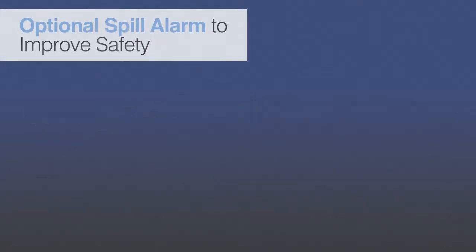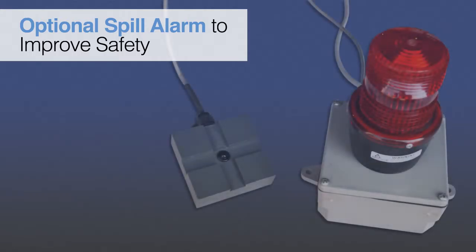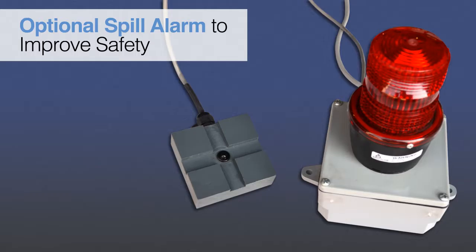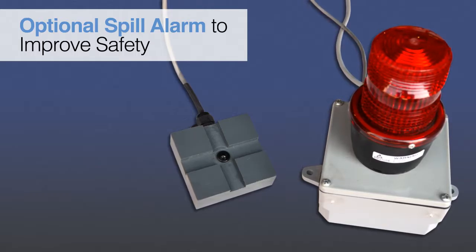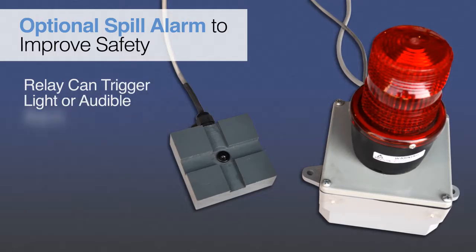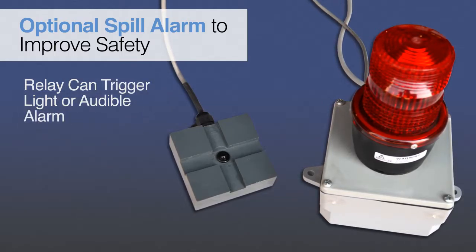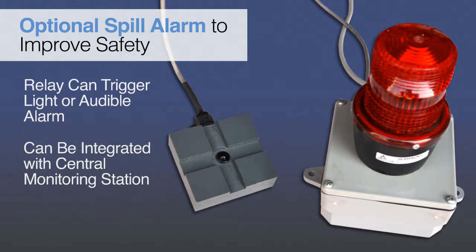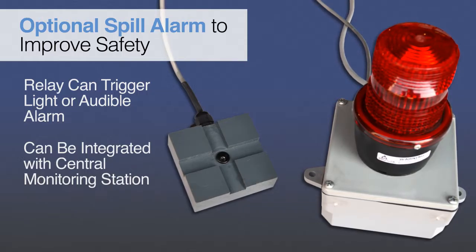Ideal for industrial and chemical process applications, the spill alarm sensor utilizes a photo transistor to detect spills and activate a relay switch. The relay may be used to trigger a light or an audible alarm. Additionally, the relay is readily integrated via PLC with other equipment or a central monitoring station to facilitate automatic shutdowns, lockouts, and other safety procedures.